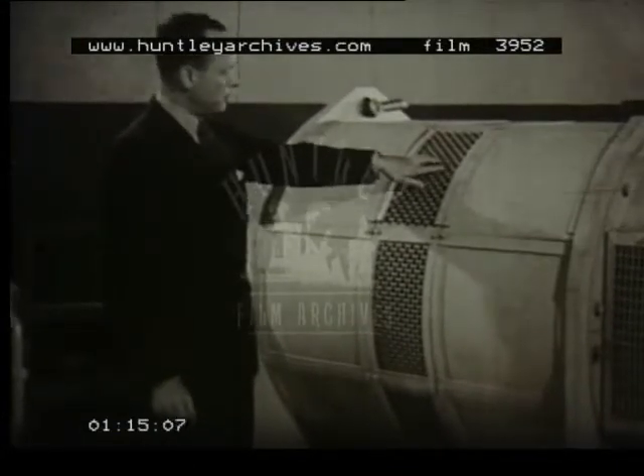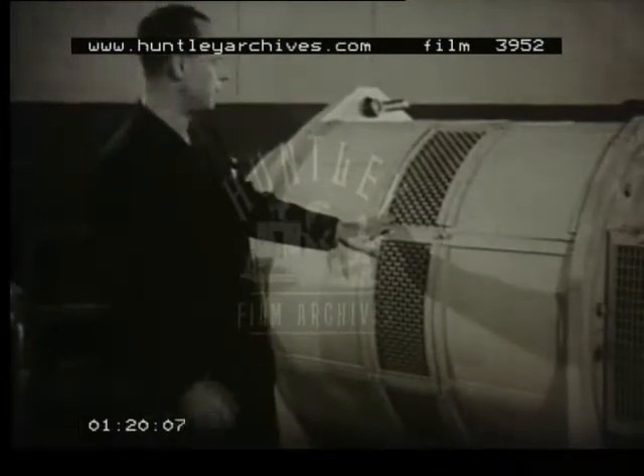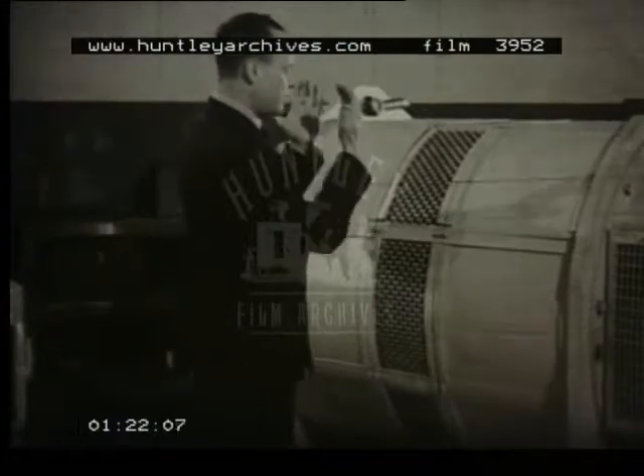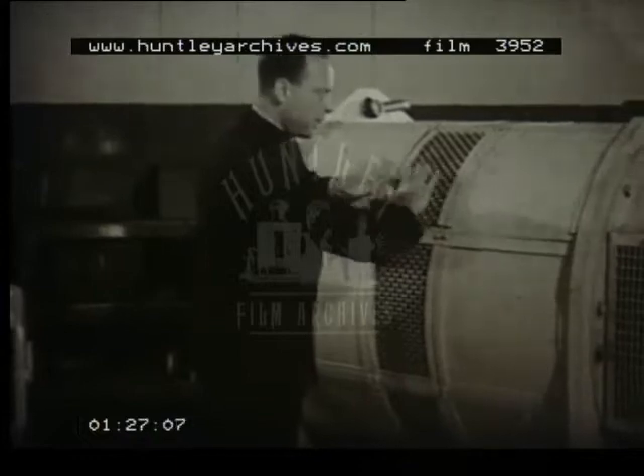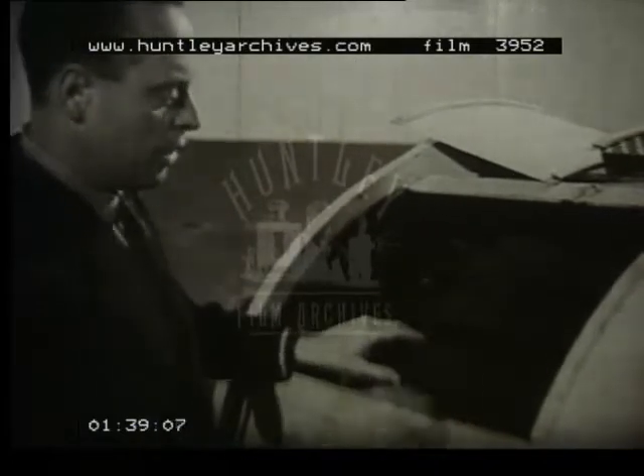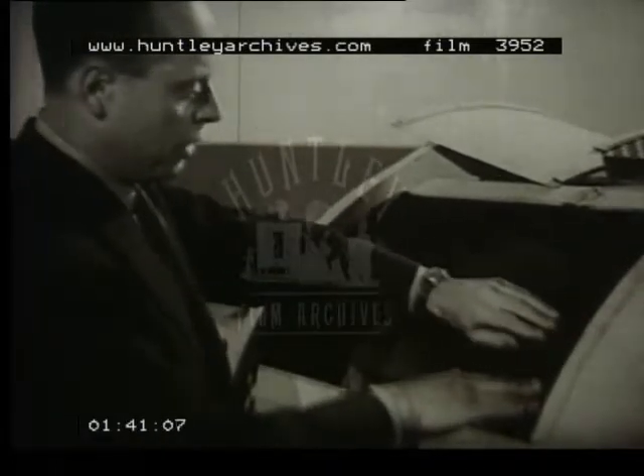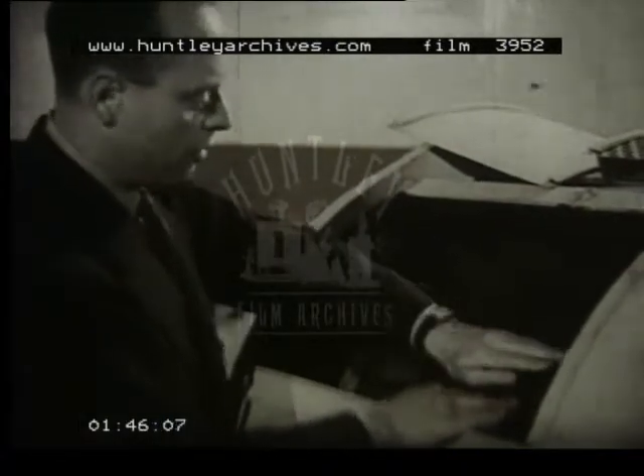Now, in this machine we have a unique system of ventilation which I'd particularly like to describe to you. Here, you see, we draw in the air in the center of the machine, and it passes along ducts, which I'll now show you. By an ingenious device, we cut these channels out of the depth of the lamination. And in this portion here, we have a tunnel through which the internal air circulates. You will observe how easy it is to clean these channels.